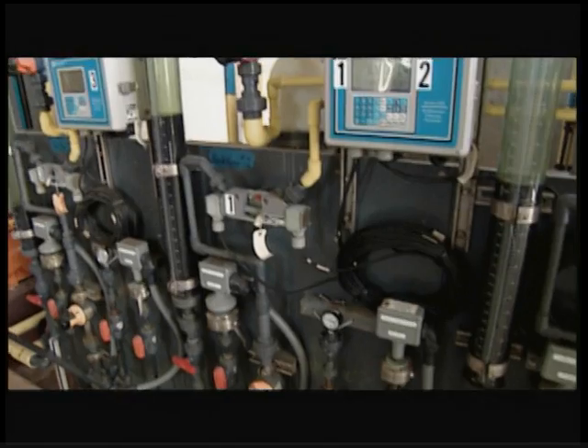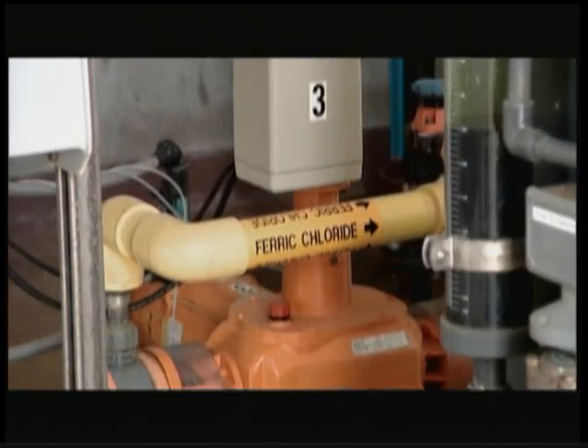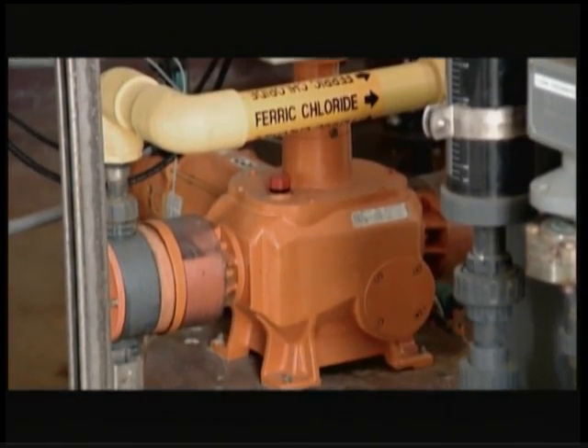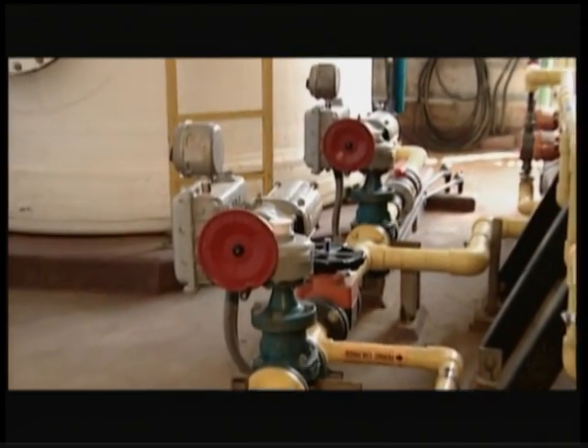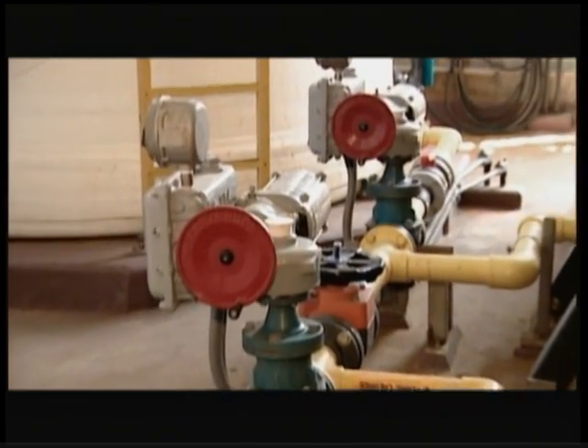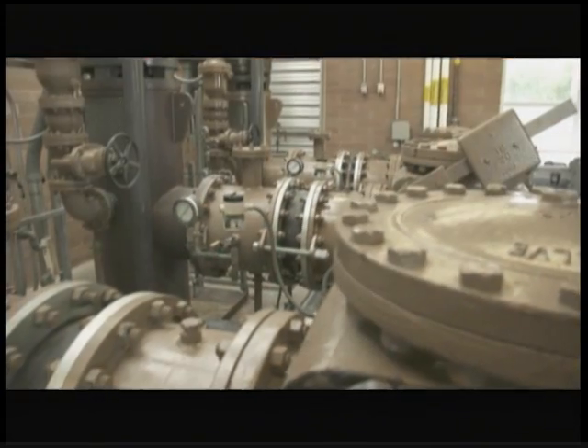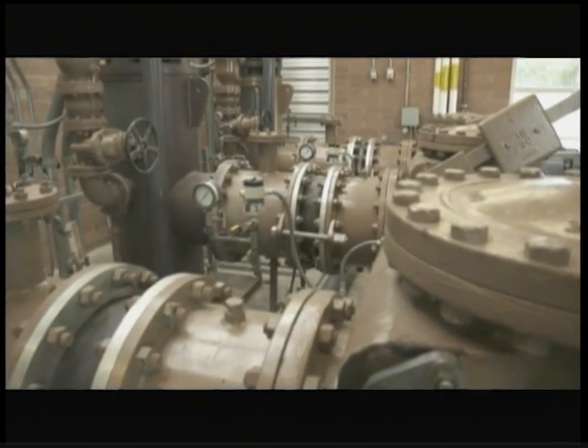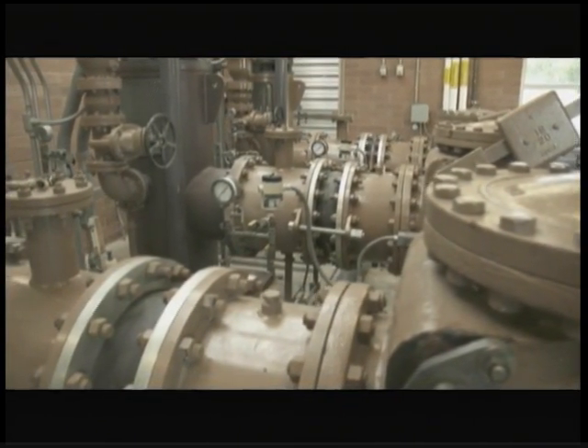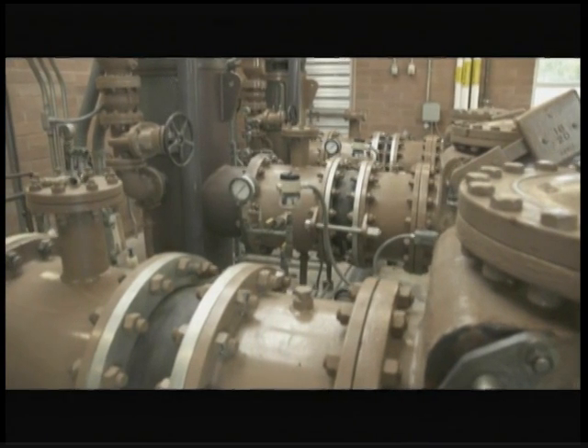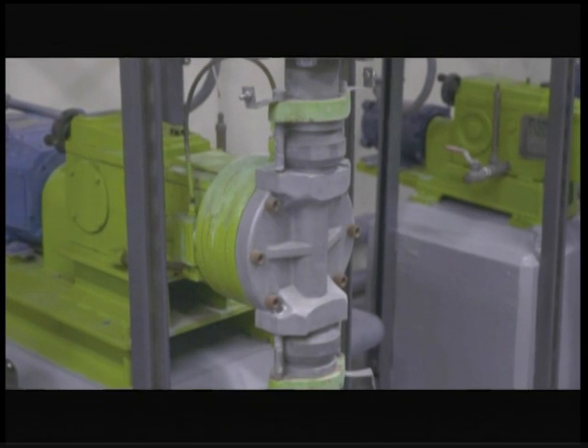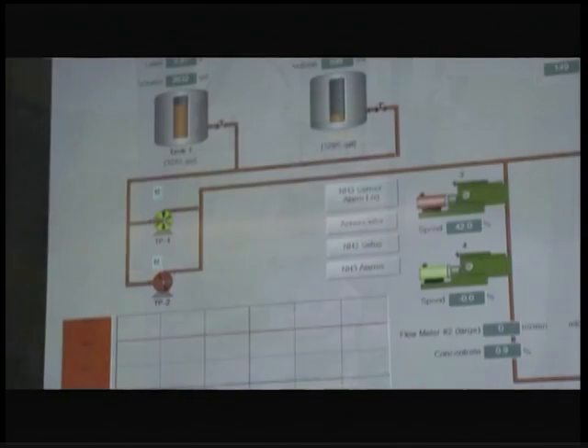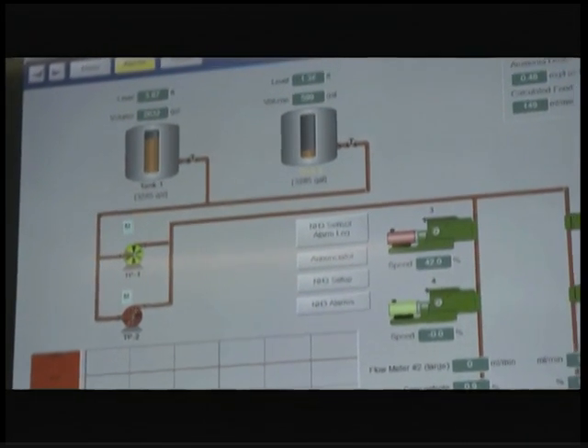Positive displacement pumps displace or move a uniform amount of fluid each cycle or revolution. Generally, they have two cavities: one an opening or expanding area that creates suction and draws liquid in, and a closing or decreasing area that pushes the liquid along. PD pumps produce the same flow at a given speed no matter the discharge pressure and are often used as metering pumps.